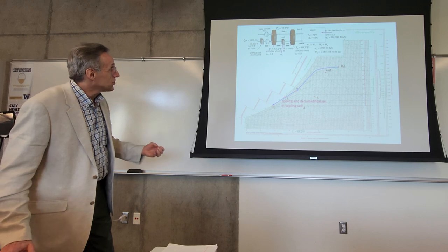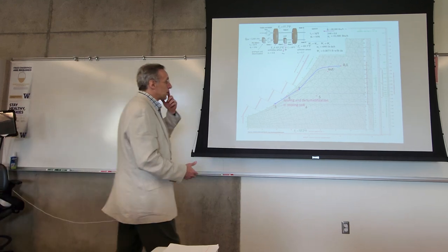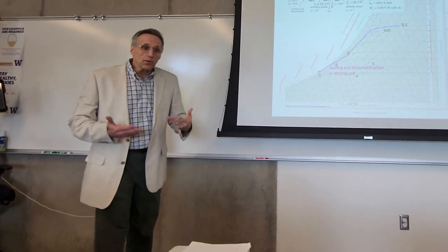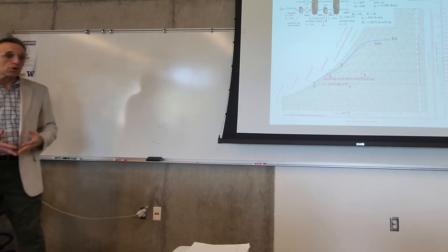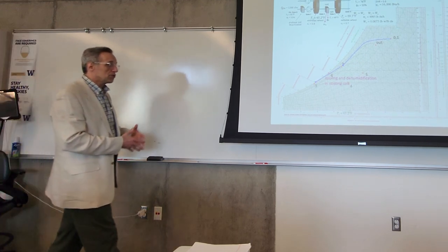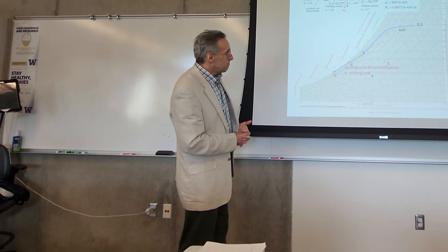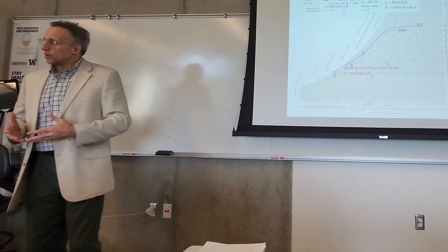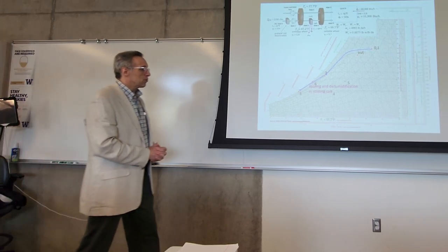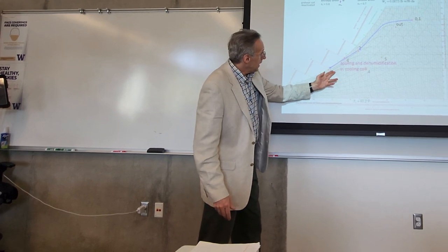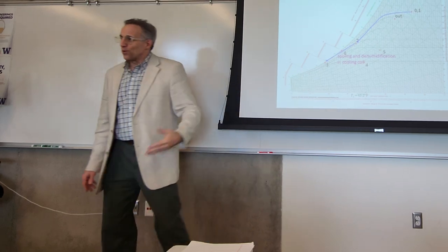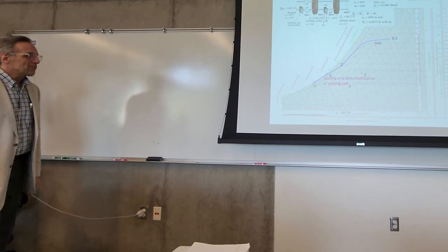Okay, so now 2 to 3, this is our refrigeration. So now we're passing through our chilled water or our refrigerant. Generally, we use chilled water. Chilled water works better with DOAS compared to just direct refrigerant. We have better control over the chilled water flow through our cooling coil than we do with refrigerant. And so we come out at 3, and now we're really cold. We're cold and dry. Good stuff, right?